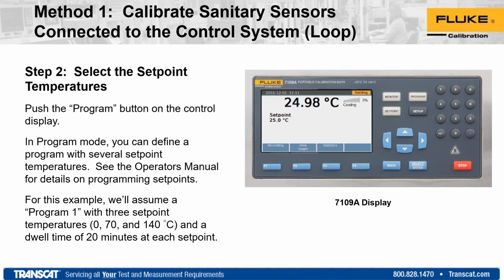All right, the next piece of the test would be to set up your set points. You can set these up manually, but the units themselves have built-in programs. They're pretty nice in that you can define several different test points, soak times, and a variety of ramp soak type options. This can help someone who is doing multiple tasks on a job. In our example, we're going to test with 3 points with a dwell time of 20 minutes at each point, and then move to the next. So we're going to program the bath to 0 in the bath program. Then it will come up, stabilize, soak for the 20, and then move to that 70 point.